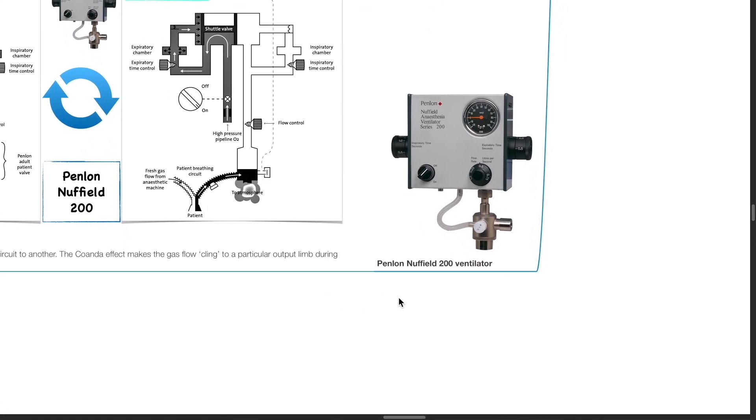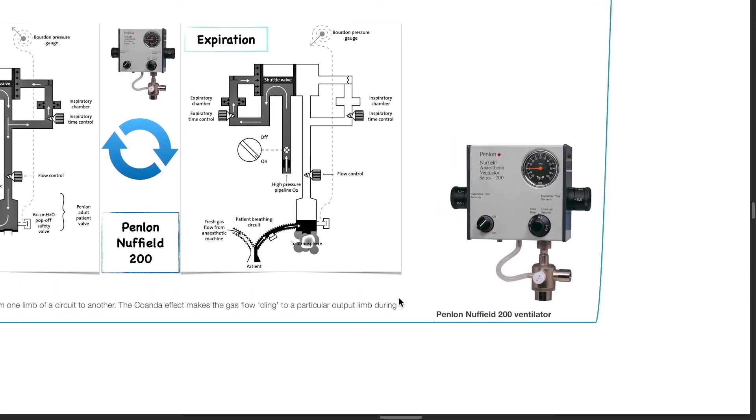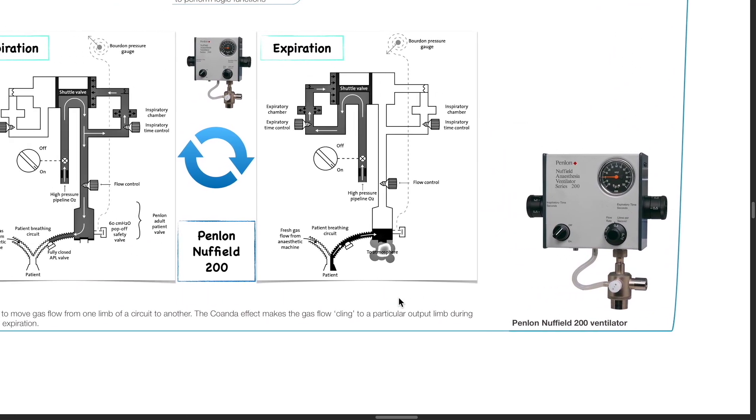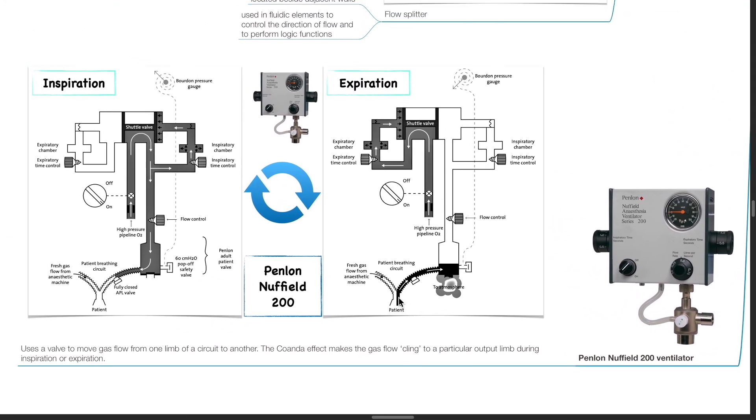The Penlon Nuffield 200 ventilator is an example of a ventilator that uses fluidic control circuits. In this ventilator, a valve is used to move gas flow from one limb of a circuit to another. The Coanda Effect makes the gas flow cling to a particular output limb during inspiration or expiration.